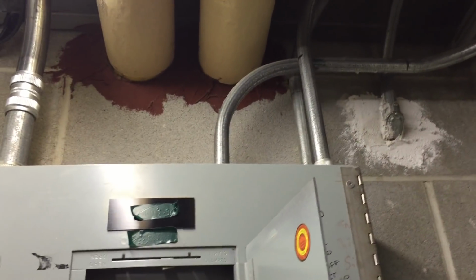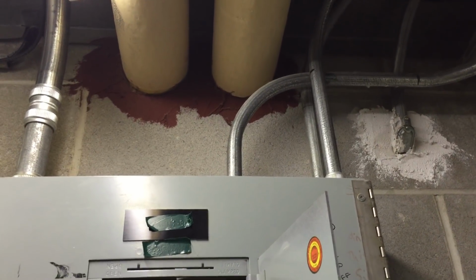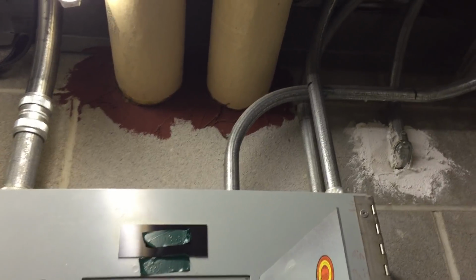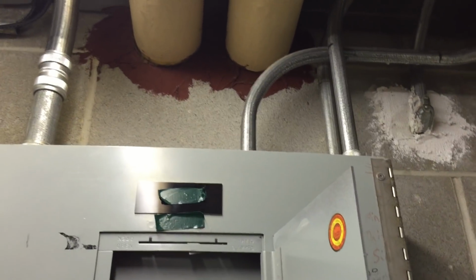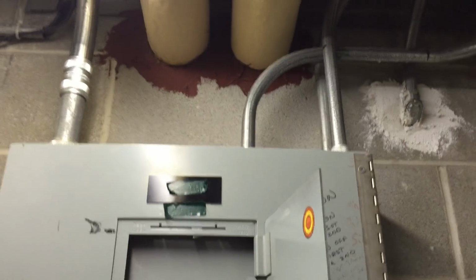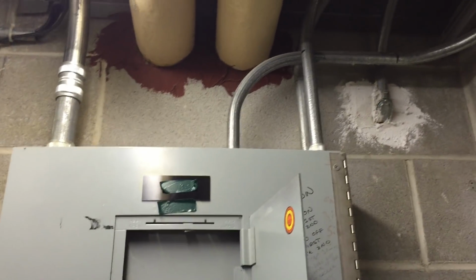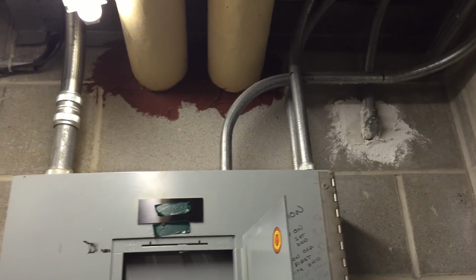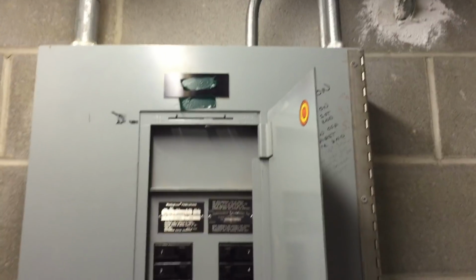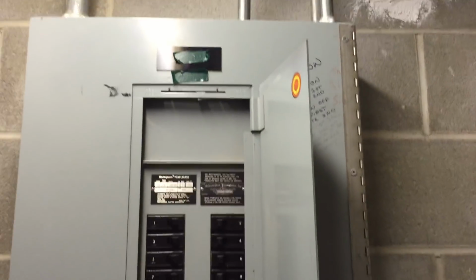And that's certainly not 6 feet. That's only maybe a foot and a half, 2 feet at most. So those have to move, or the panel board has to move. Any leaks or condensation in those pipes could end up inside the panel, and that could cause real problems.